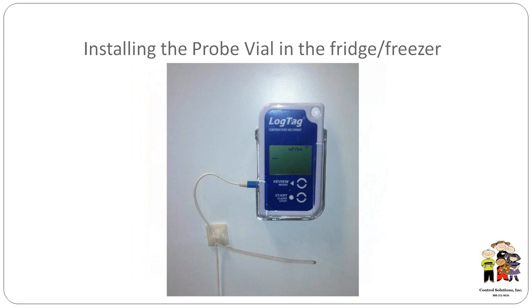Once I have the cable outside my refrigeration unit, I'll put the logger into the wall mounting bracket. I'll secure the cable so I know how much distance I have, placing the logger somewhere easy to read and operate, making sure it's straight, about 6 to 8 inches from the installation. I'll use another sticky back to secure the wire, so that when I remove the logger to evaluate storage and handling, the wire won't fall and get dirty or broken.